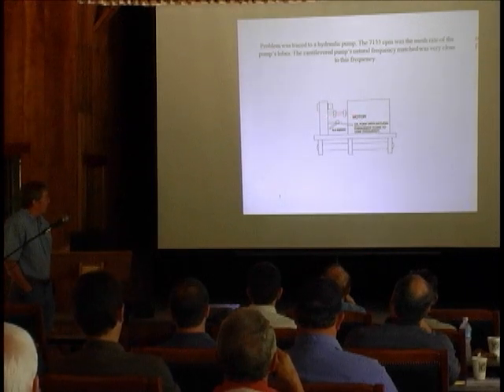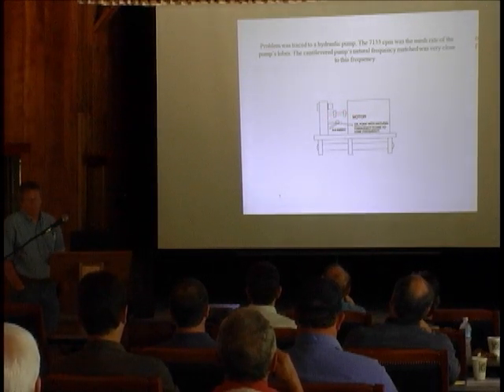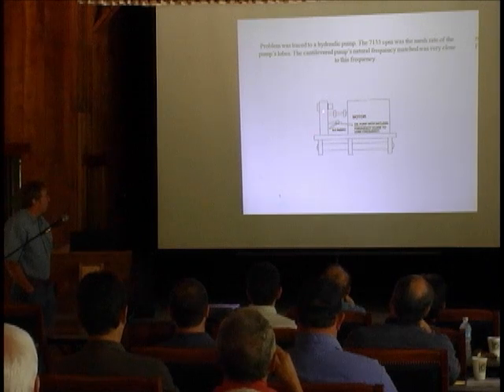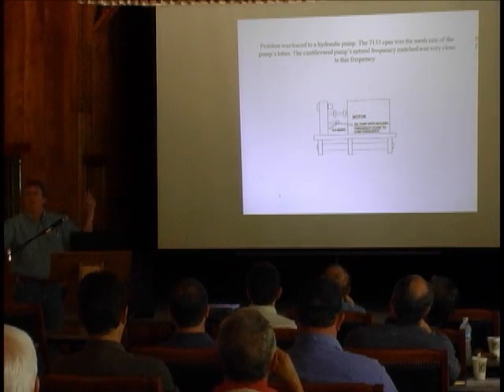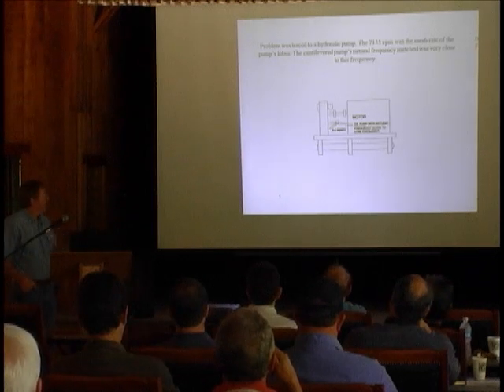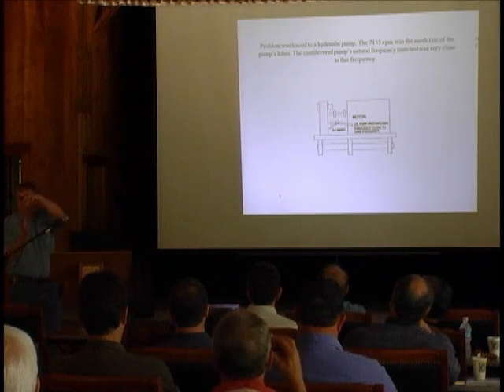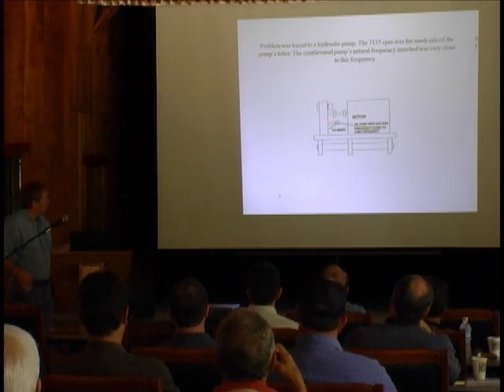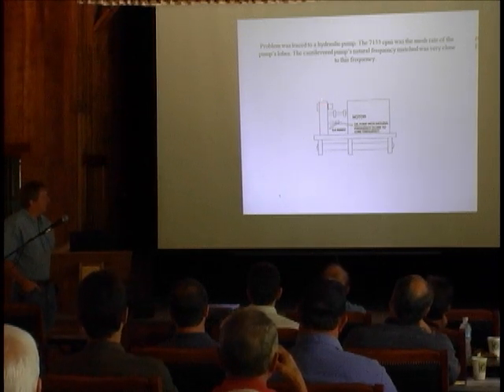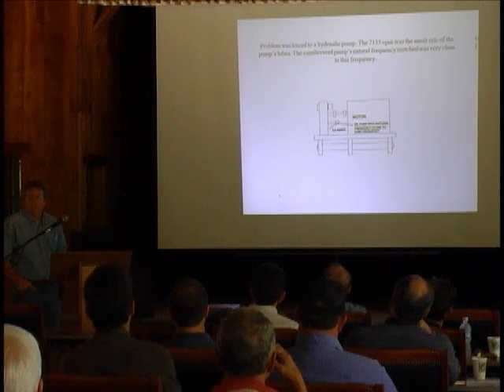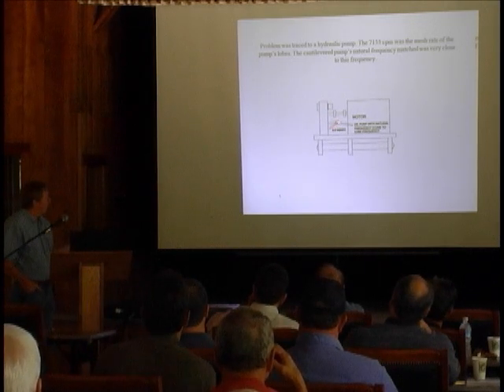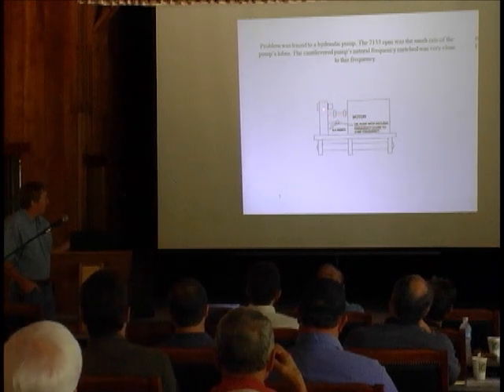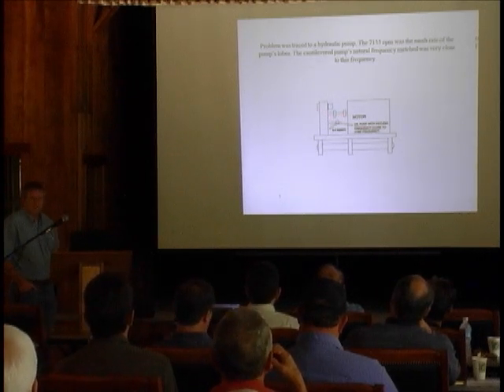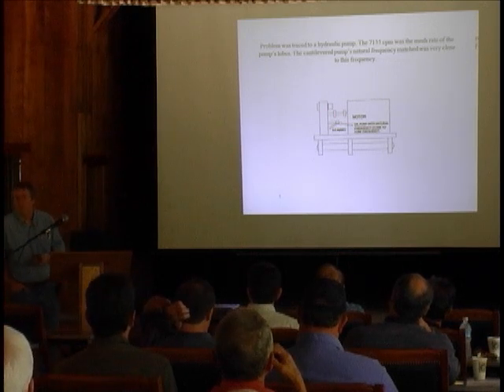But they're motor-driven, and you've got an 1800 or 3600 RPM motor. And then you've got a big bull gear in here. I mean, it's a big old bull gear. It has about 200 or 300 teeth on it. And then it's driving pinions that have your high-speed compressor elements. They're only about that big. So on one of my high-speed components, it runs 10 or 11,000 RPM. I've got 4 times the input speed on that. And it just doesn't make any sense, but it's enough that it's tripping the unit.